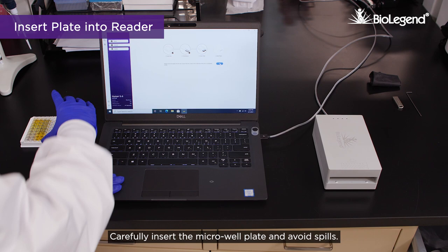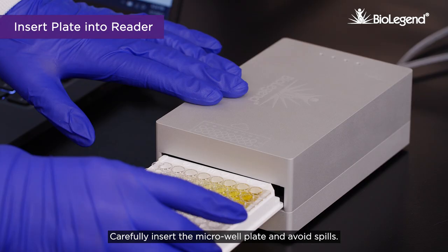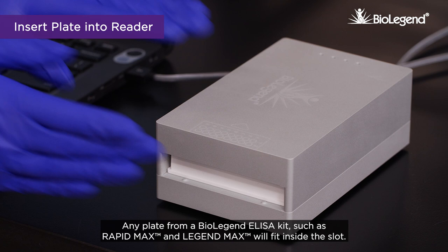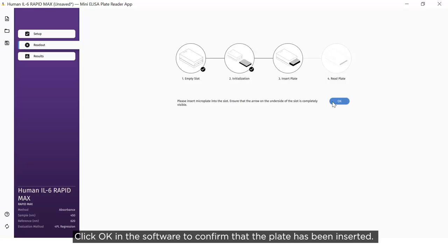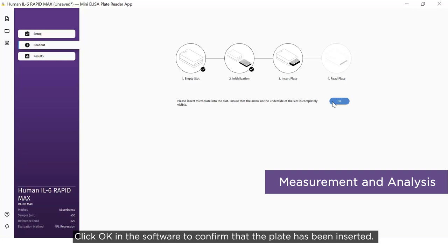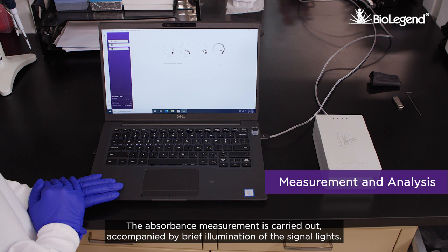Carefully insert the microwell plate and avoid spills. Any plate from a BioLegend ELISA kit, such as Rapid Max and Legend Max, will fit inside the slot. Click OK in the software to confirm that the plate has been inserted. The absorbance measurement is carried out, accompanied by brief illumination of the signal lights. When measurement is complete, the results will be shown.